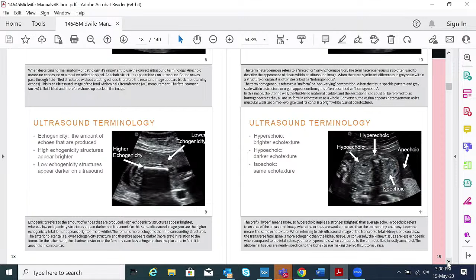So we go to how ultrasound images are created. Of course, you must have your ultrasound equipment, and then you must have what we call a probe. Then the ultrasound system creates a sound wave and listens to the returning echo. The returning echo goes through the probe, and then you have very strong echoes coming up. So we call that the strength and brightness. Stronger echoes appear brighter, and weaker echoes appear darker.